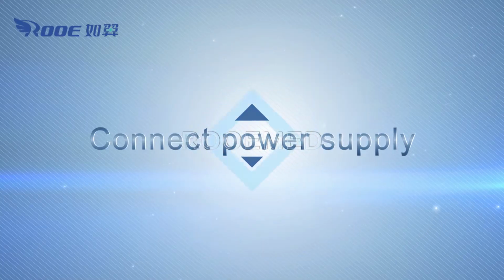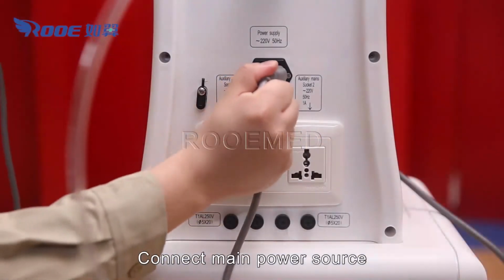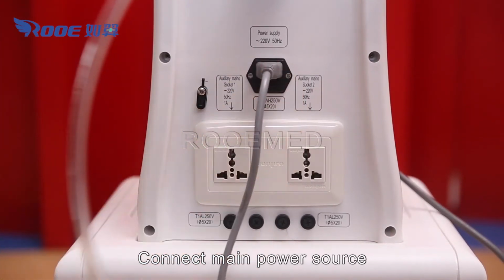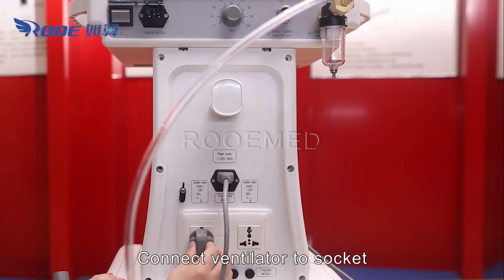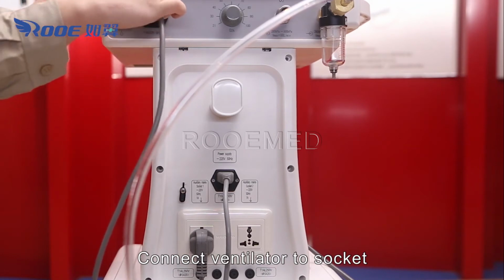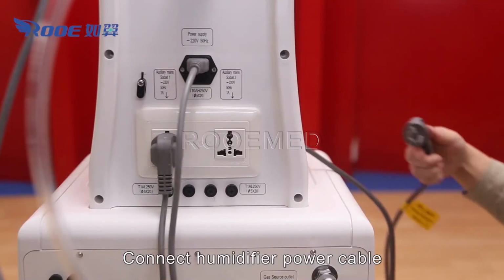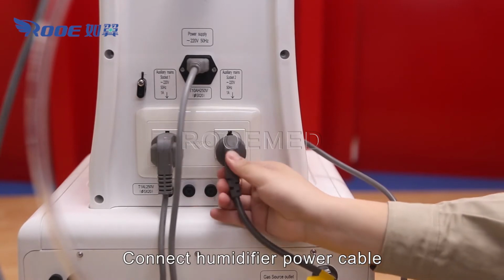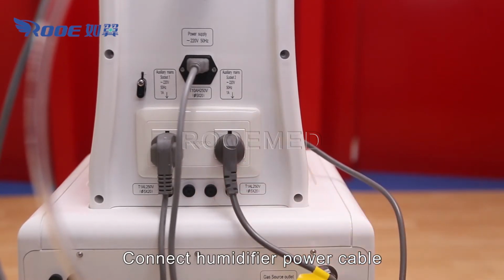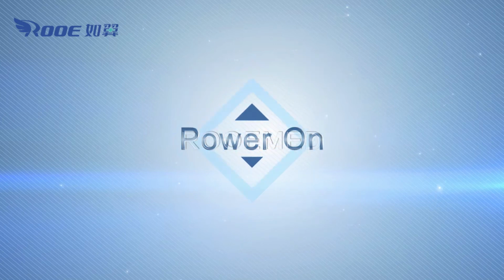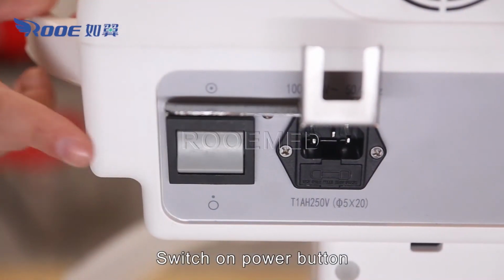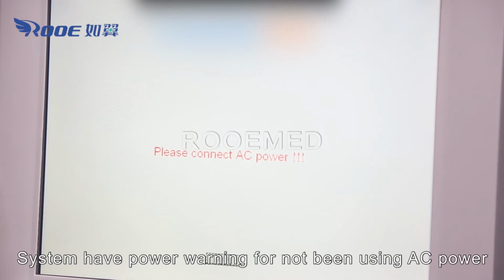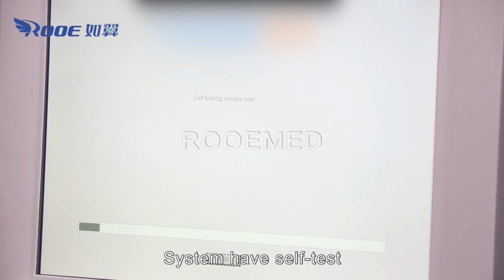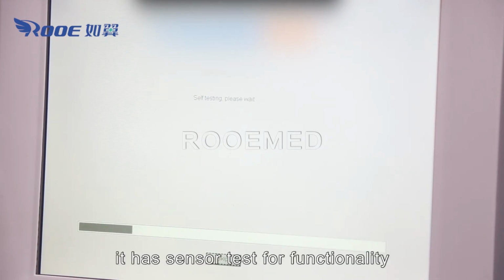Connect power supply. Connect main power source. Connect ventilator to socket. Connect humidifier power cable. Power on. Switch on the power button. The system gives a power warning for not using AC power. The system performs a self-test. In this mode, it has a sensor test for functionality.